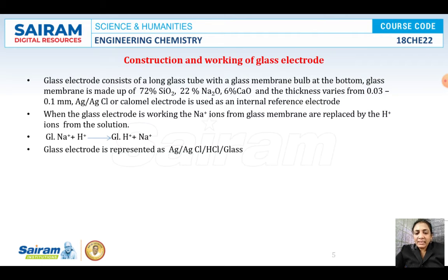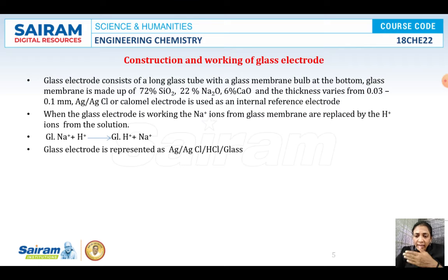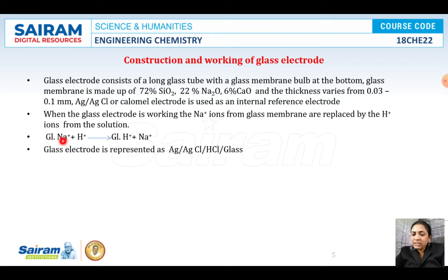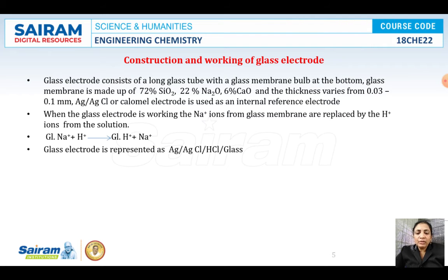When the glass electrode is working, the Na+ ions from the glass membrane are replaced by H+ ions from the solution. The glass electrode responds specifically to H+ ions in the solution. In the glass membrane, sodium ions are exchanged with H+ ions, giving: Glass-Na+ + H+ → Glass-H+ + Na+. After long-term usage, when all the Na+ is completely replaced by H+ ions, the electrode starts showing error.